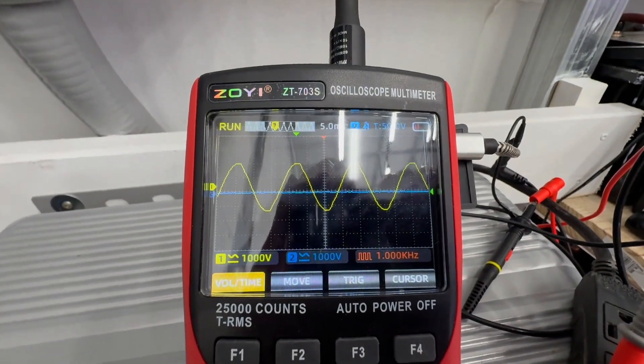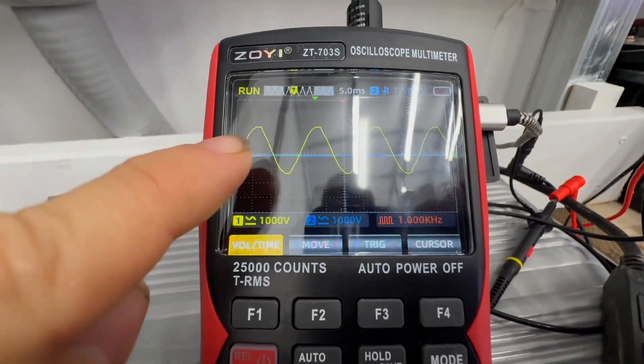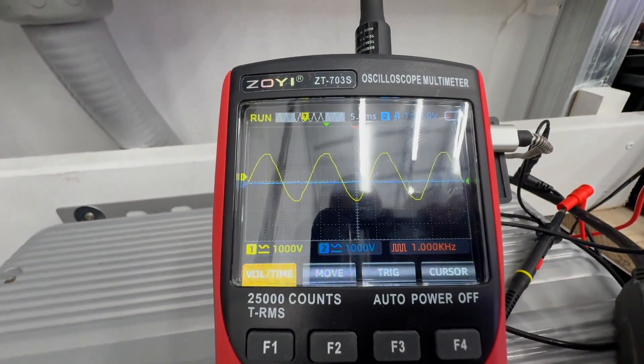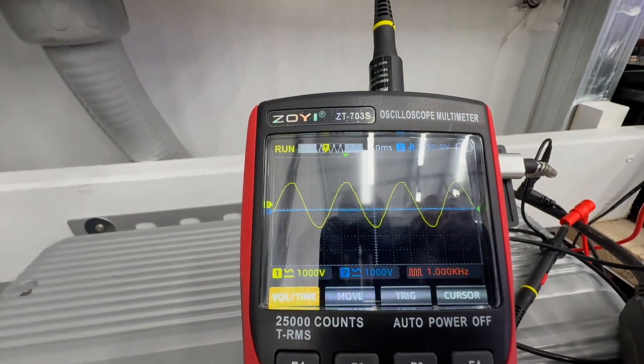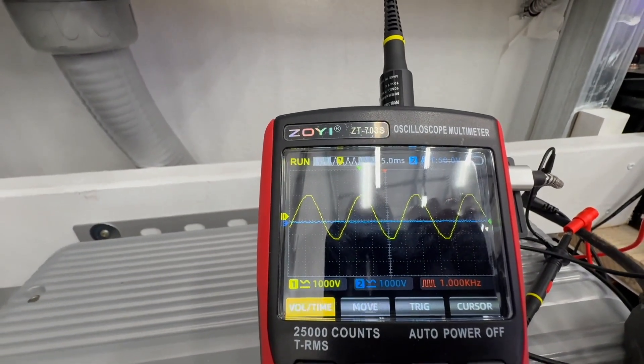Here's the output of my two 12,000 XPs running in parallel right now. It is very, very clean — no jagged edges, nice and smooth at the top and bottom peaks. You can see both inverters running in parallel shown in yellow.